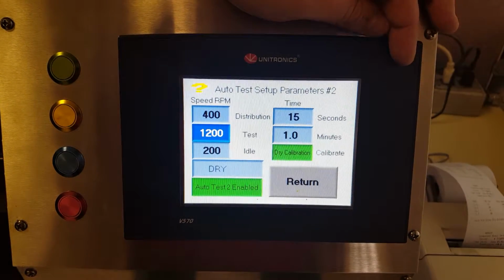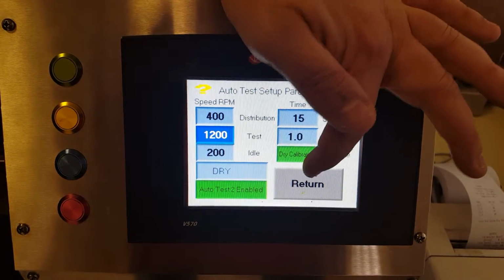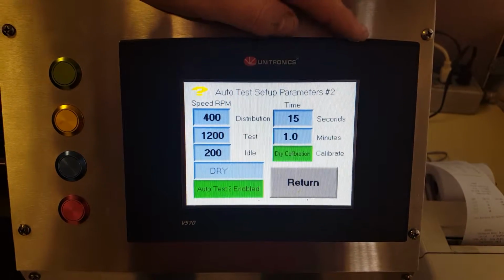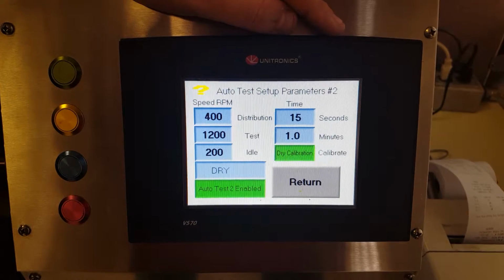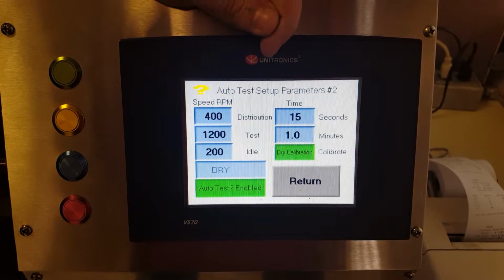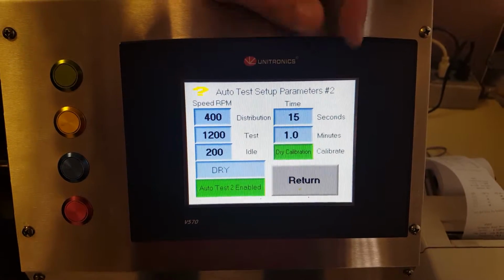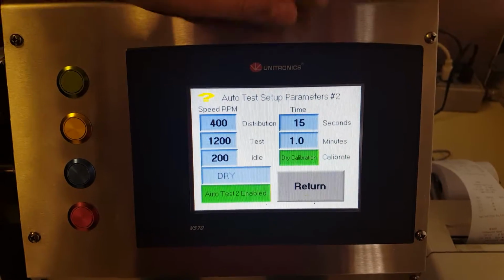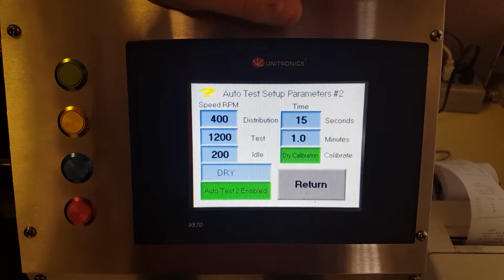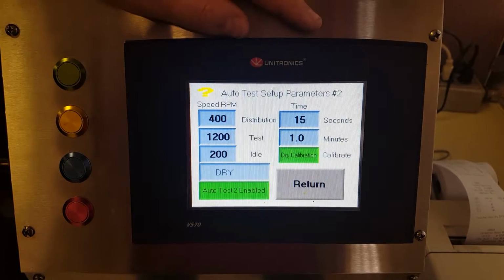To change that on the automatic test setup, you can select dry or ink. Once this is set up, the PLC will remember these parameters, and anytime you select auto test number 2, which is the one we're in here, you'll get exactly these parameters. Same thing with auto test number 1 - they can be customized differently however you want.